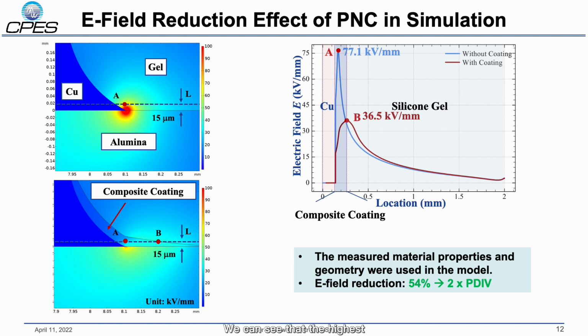We can see that the highest electric field was reduced from 77.1 kilovolt per millimeter to 36.5 kilovolt per millimeter. The measured material properties and the geometry were used in this model, and we found the E-field reduction is about 54%, which matches the PDIV improvement we observed in the experiments.